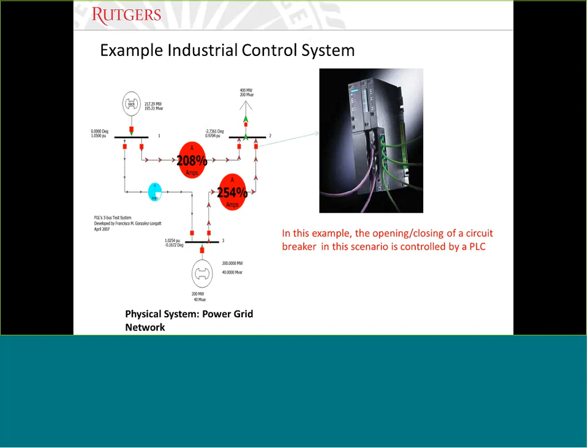On top of this you'd have an HMI system, or a SCADA center, monitoring the PLC values and sending actuation commands. You may also have a programmer, possibly air-gapped from the system, allowed to change the PLC configuration and the control logic loaded onto the PLCs. These two connections typically have different access rights: the programmer can change the configuration and control logic, while the SCADA center usually only monitors and sends control commands.